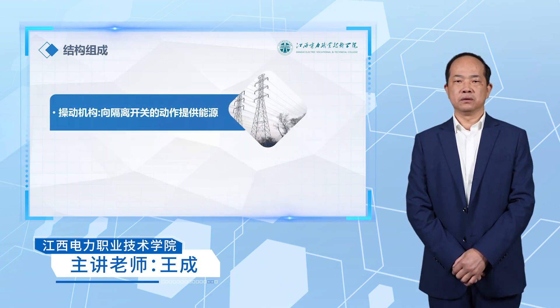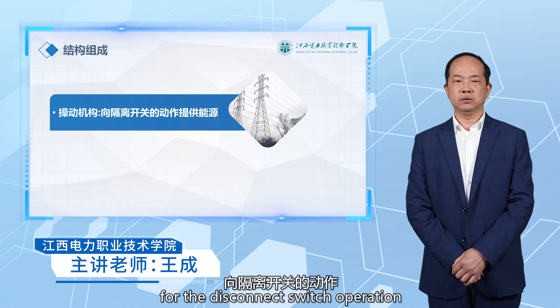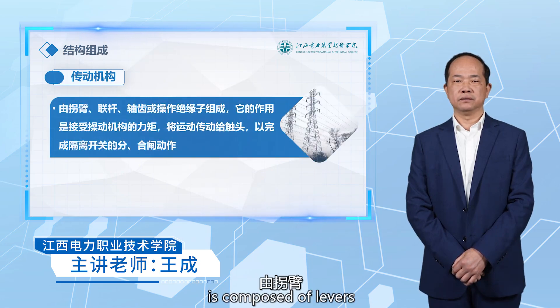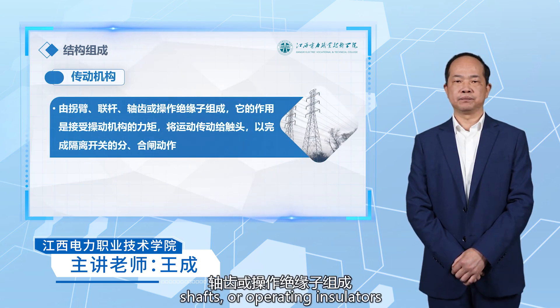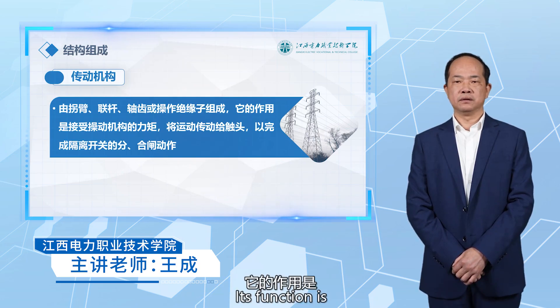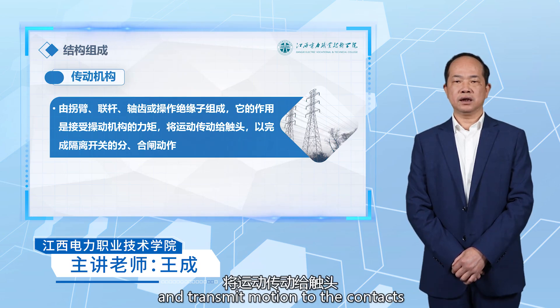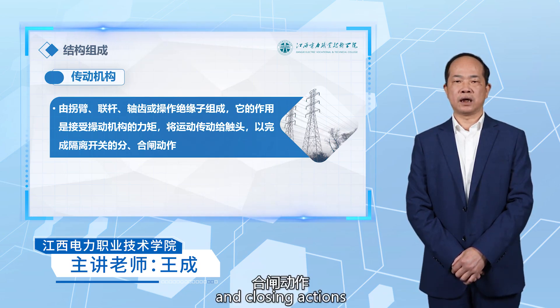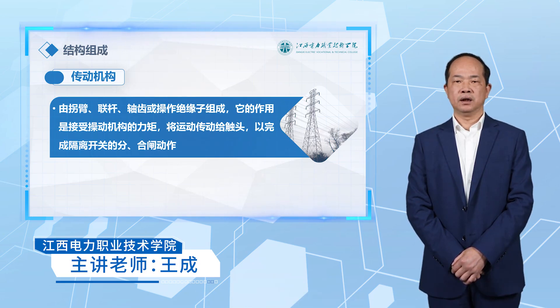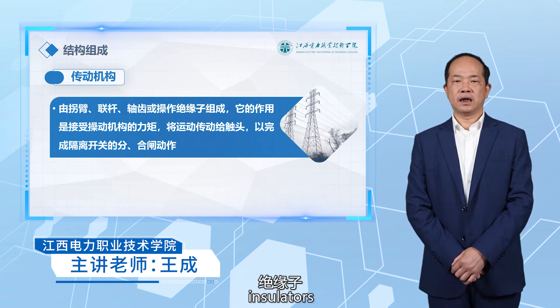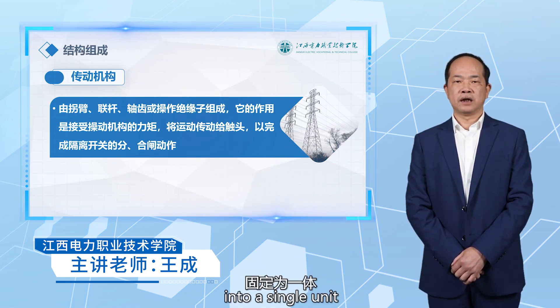Third, the operating mechanism, which provides the energy for disconnect switch operation. Fourth, the transmission mechanism, composed of levers, linkages, shafts, or operating insulators. Its function is to receive the torque from the operating mechanism and transmit motion to the contacts to complete the opening and closing actions. Fifth, the support base, which provides support and fixation, integrating the conductive part, insulators, transmission mechanism, and operating mechanism into a single unit.